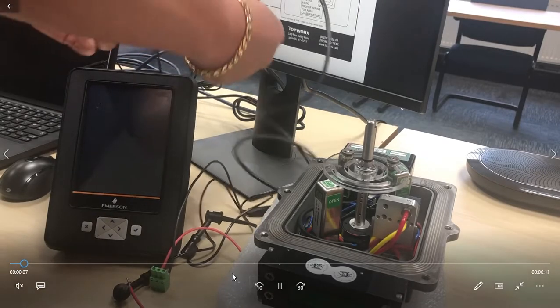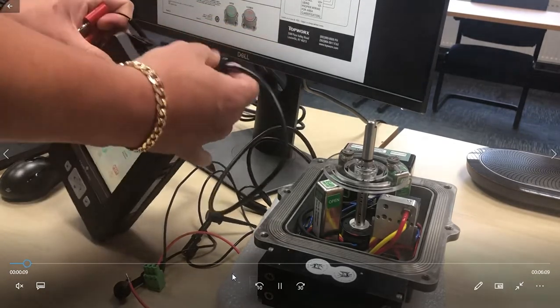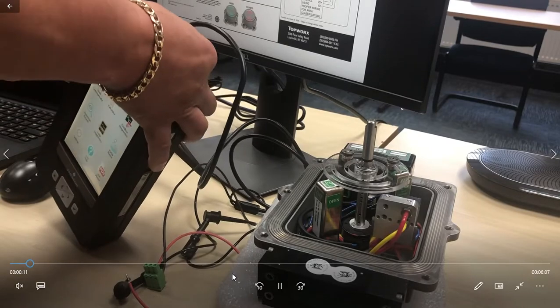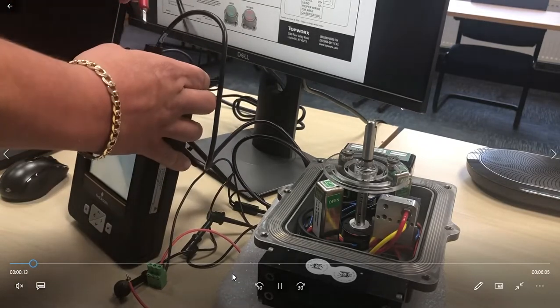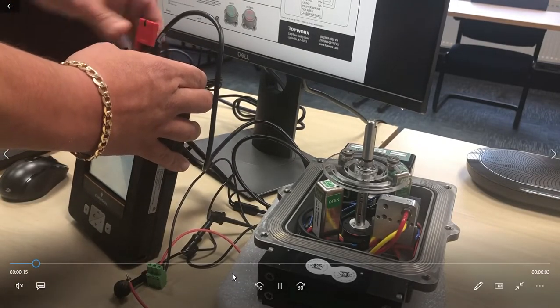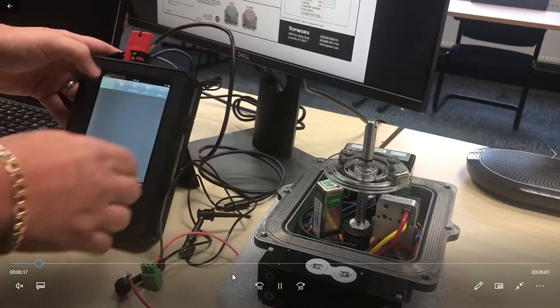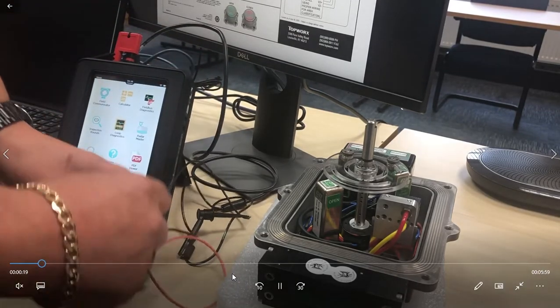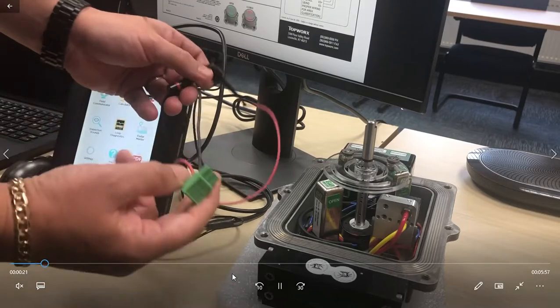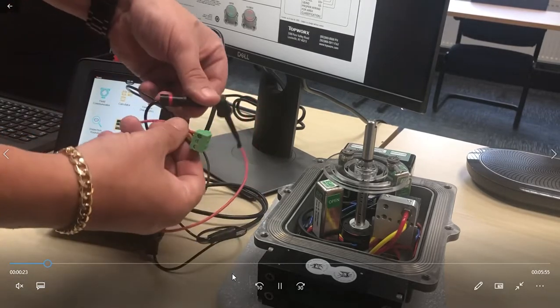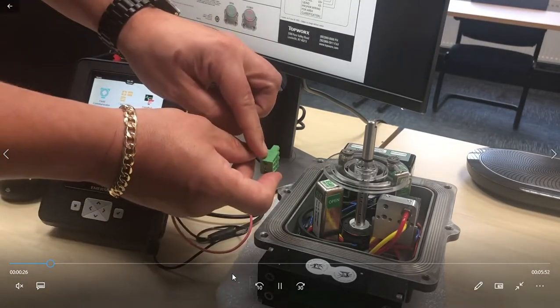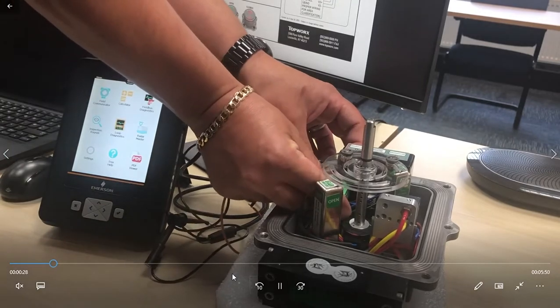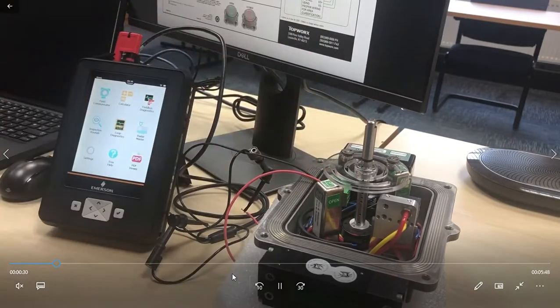So first of all, we need to connect the TREX device to the Foundation Fieldbus ports on the top of the TREX, ensuring that we use the additional connector to connect power. Then we must ensure polarity is correct by making sure that the red is connected to the red lead, which is the positive side of the Foundation Fieldbus connection.